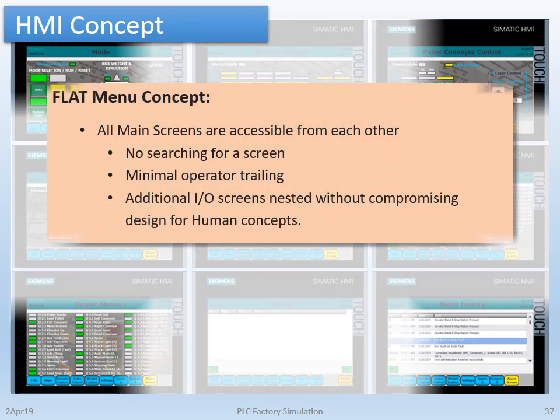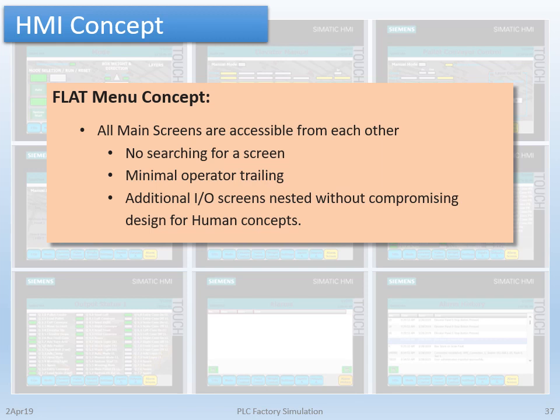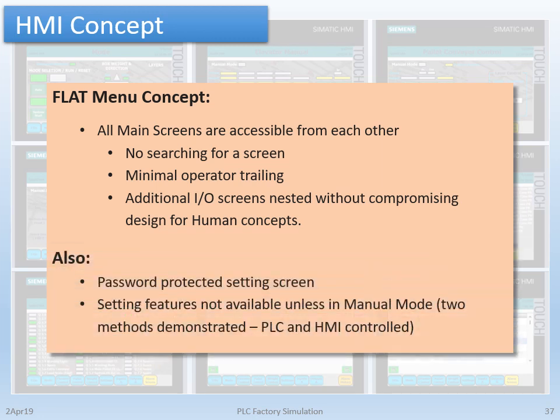So what is a flat menu concept? Simply stated, all main screens are accessible from each other. There's no searching for screens, there's minimal operator training involved, and additional IO screens can be nested without compromising the design for human concept. I've also included a password-protected settings screen with features not available unless in manual mode. So there are two methods demonstrated here — PLC controlled and HMI controlled — and I was able to embed that all into the flat menu concept.